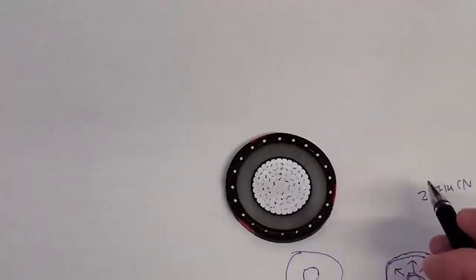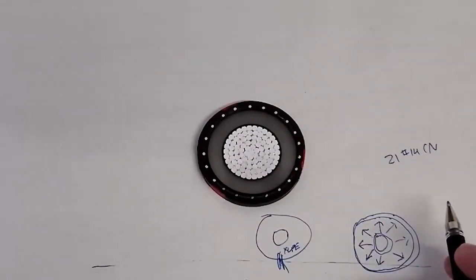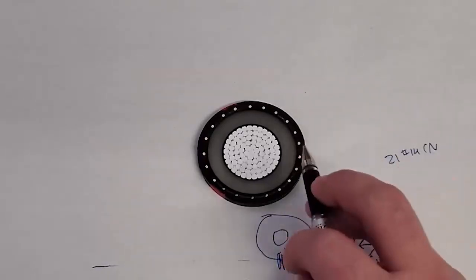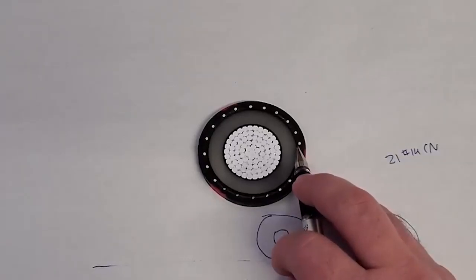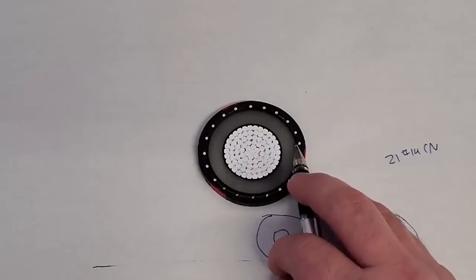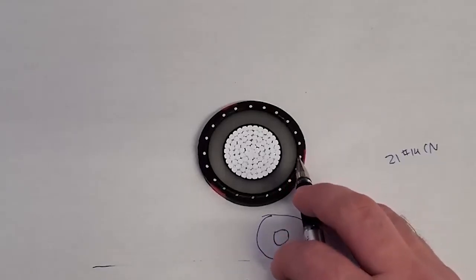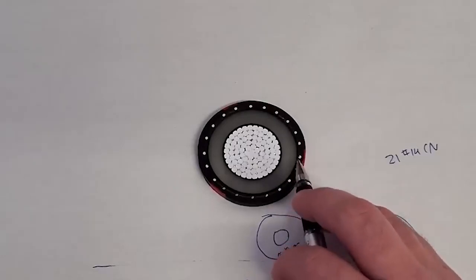So imagine a 10,000 PSI gas line. This electricity is looking for a way to jump out. And if you put even the smallest little pinhole, even something a quarter the size of a pinhole, it will jump out and it'll blow up the cable. I would say the most important layer of this cable is the insulation shield. If that gets punctured or cut or broken in any way, that flux will jump through, and the voltage will jump through the insulation to ground, and it'll blow up the cable. It's the most important part, this black area right here.